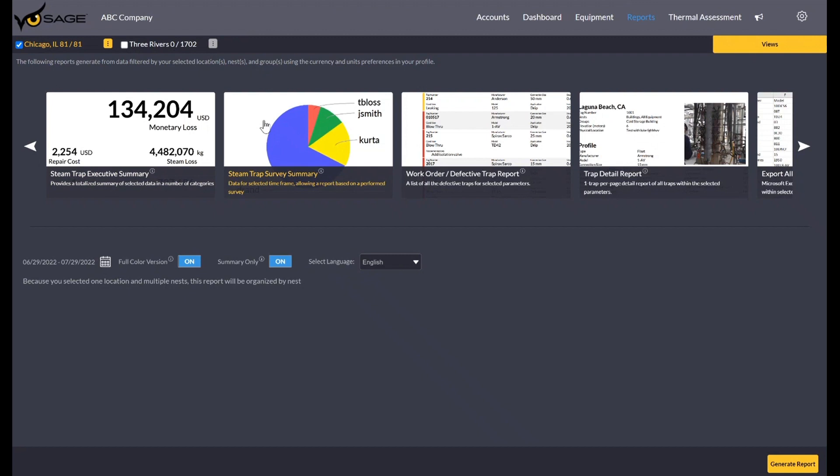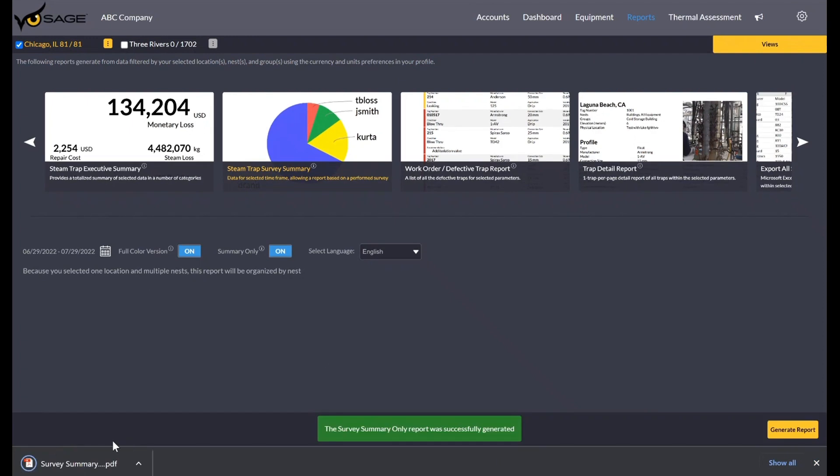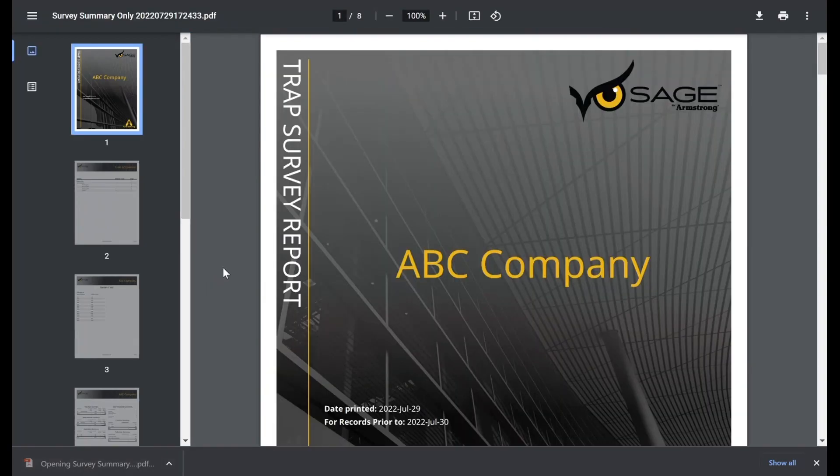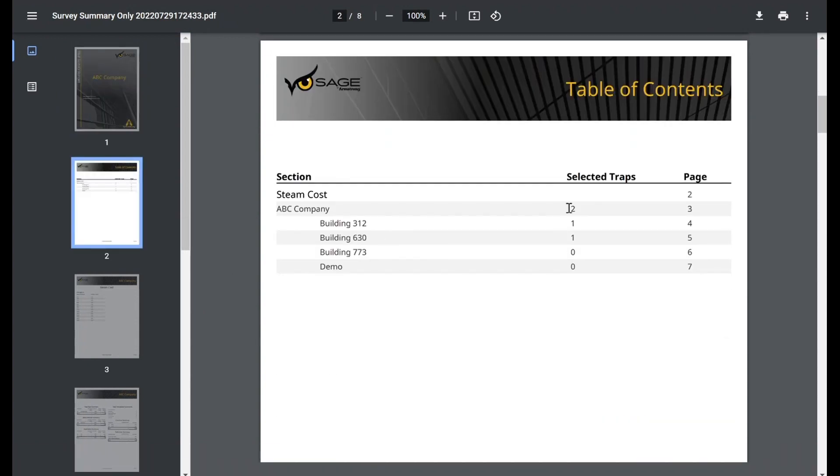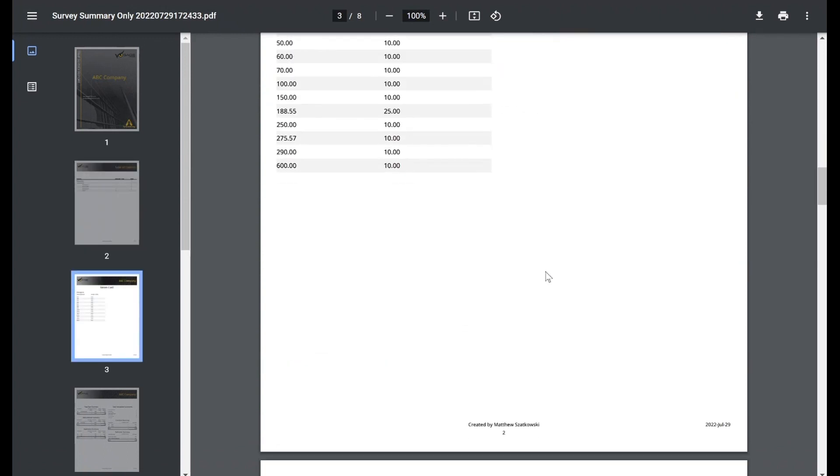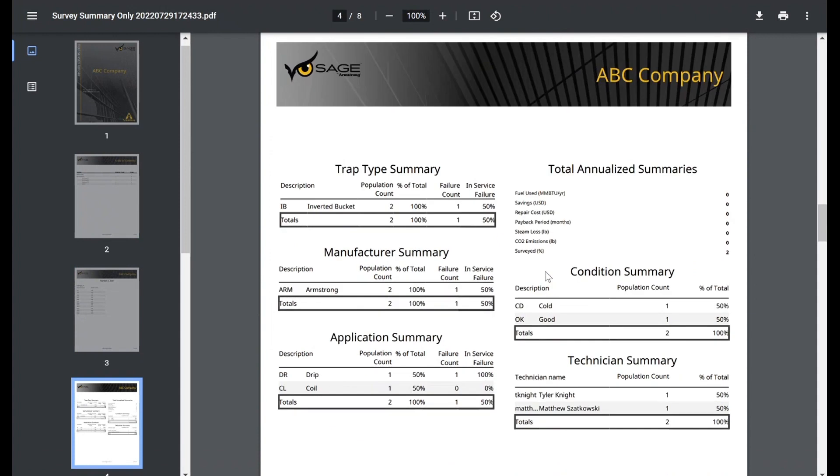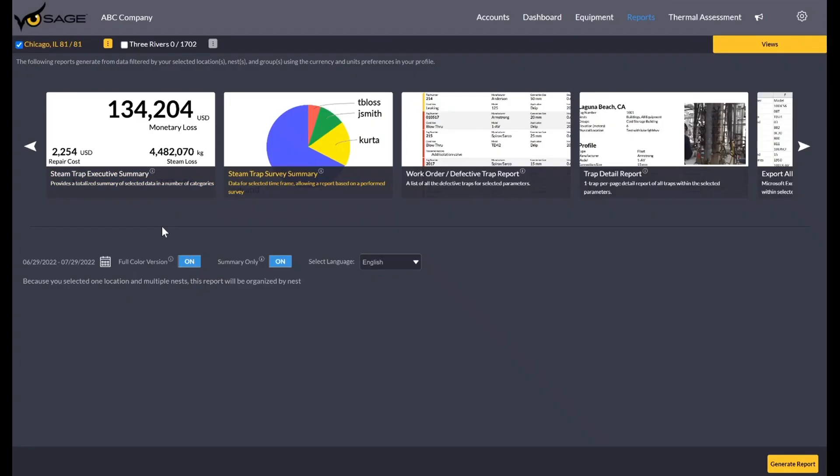The steam trap survey summary is actually the identical format. It just looks for traps that have had a survey performed on them. If I run it right now in our default 30 days, it's only going to include the steam traps that were surveyed in the last 30 days or had a condition change. I changed that one condition while I was going over that steam trap, so we would expect at least one trap to be on here. But in this case, there actually is two. So again, the format is the same. But I just wanted to show that it's focusing on just the steam traps that were surveyed in the range you set. If you set this range for one week, a full month, maybe you were surveying for a full month or updating conditions periodically throughout a month, you could run it for 30 days, you can run it for a year if you wanted to. There are reports on every condition change recorded.